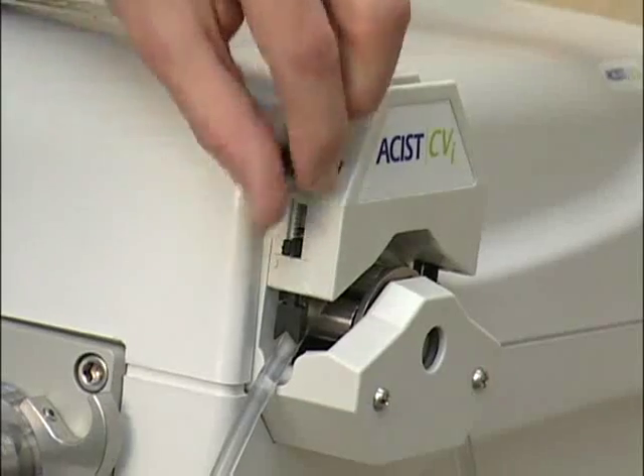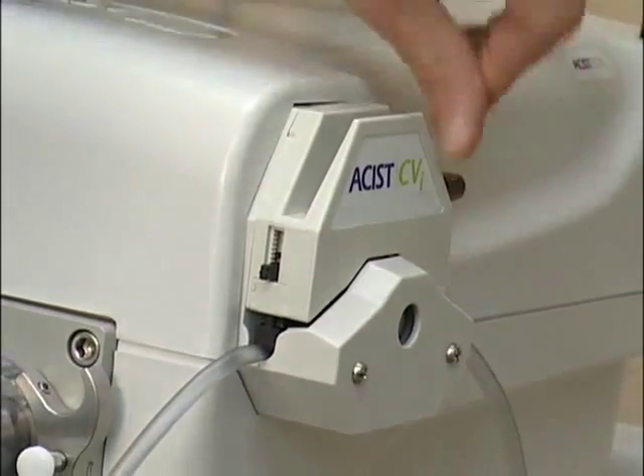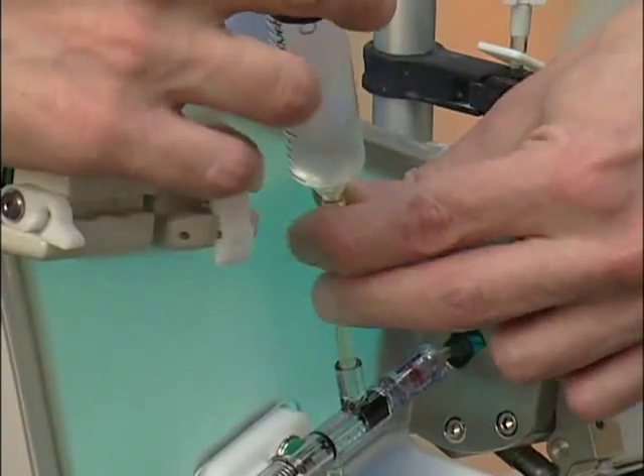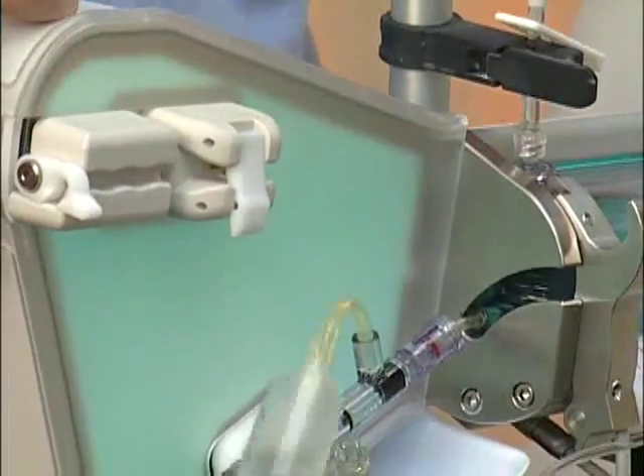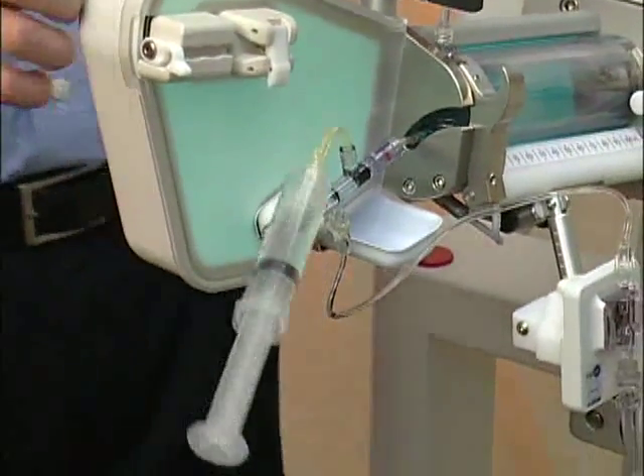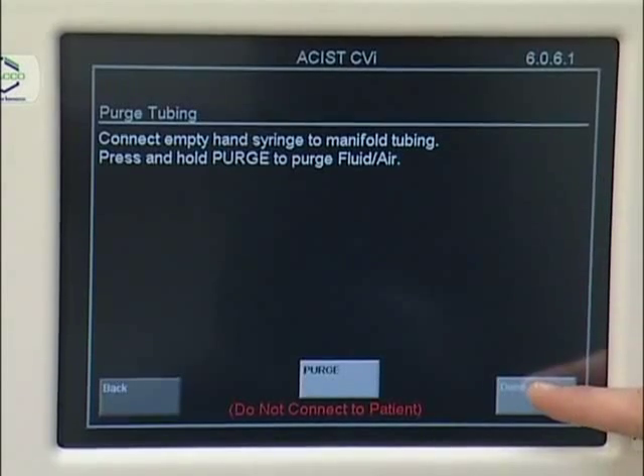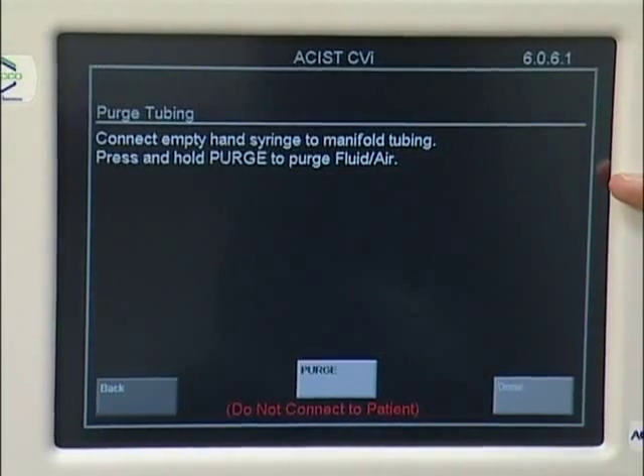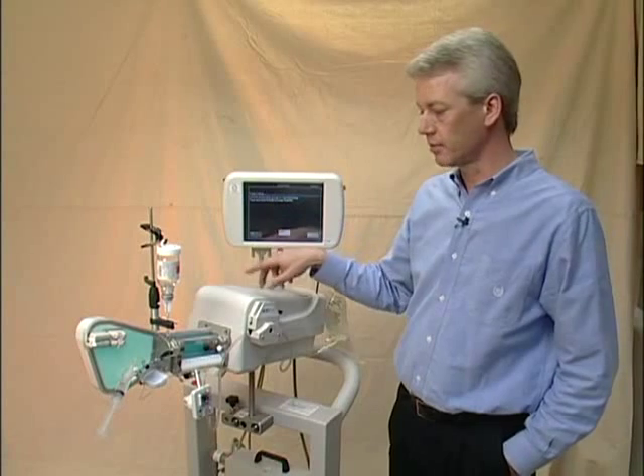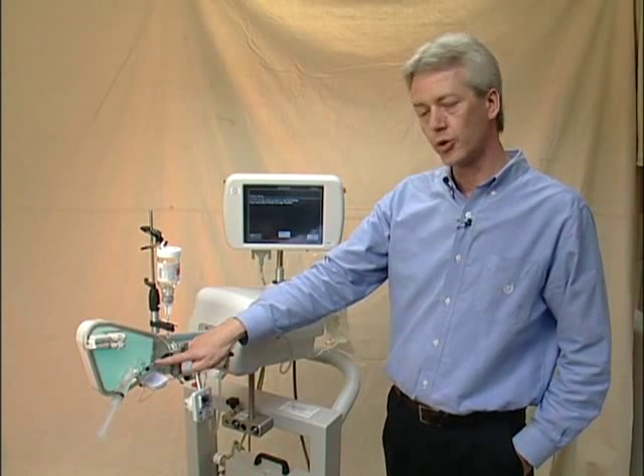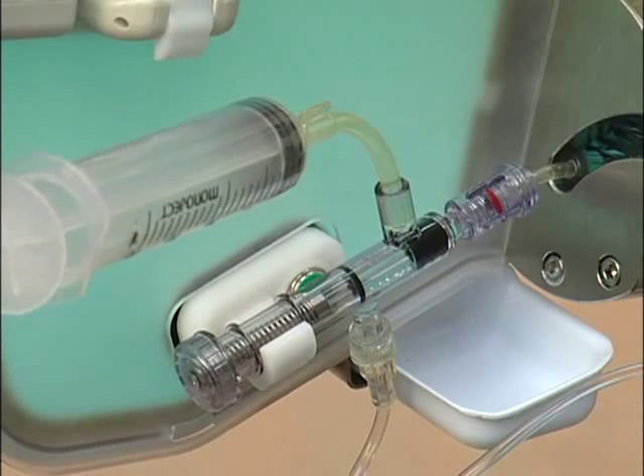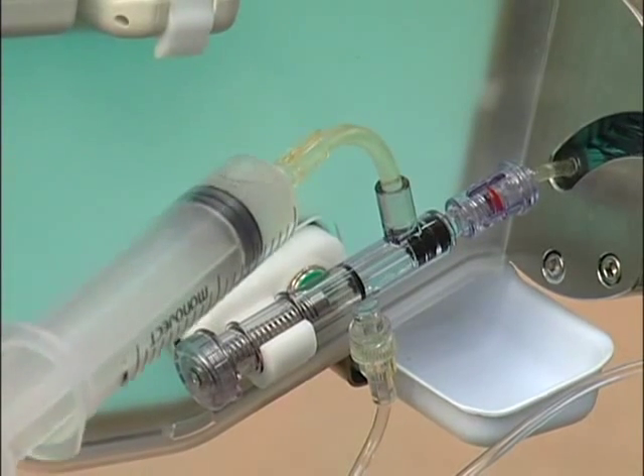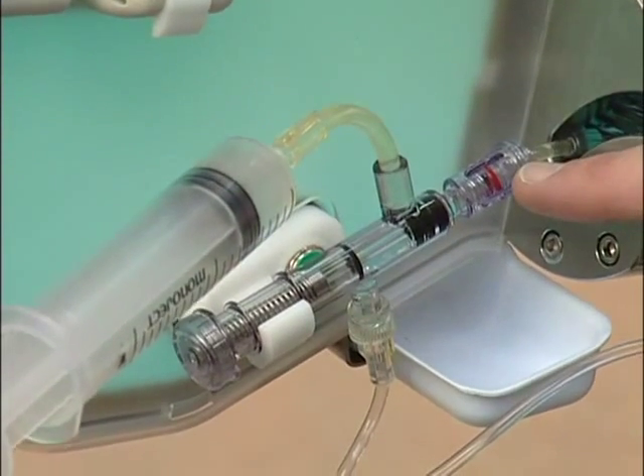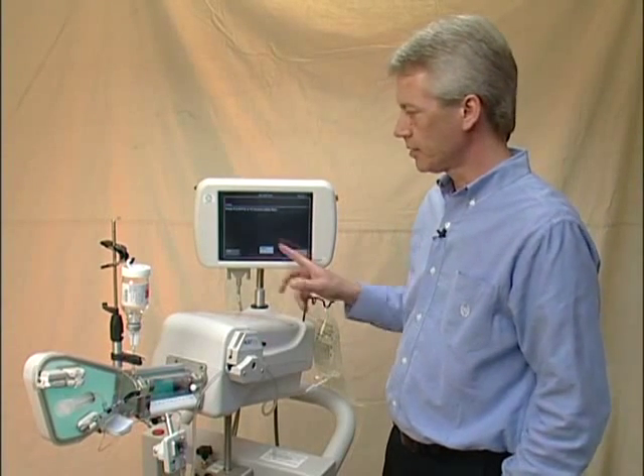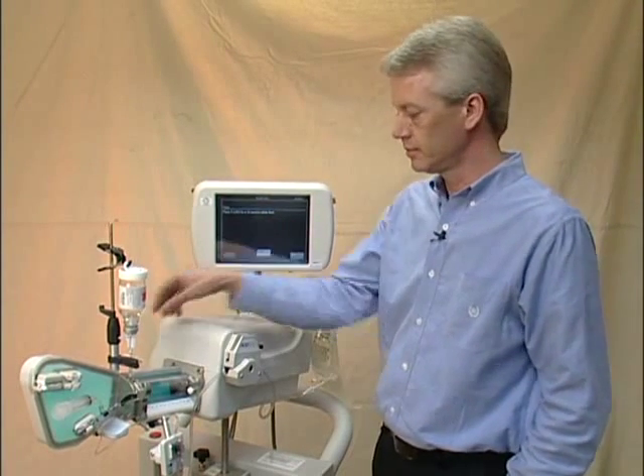Once that step is complete, then the latch can be closed. The hand syringe will be positioned on the end of the tubing until the procedure begins. Once these steps are complete, we'll press done. This brings me to the purge tubing screen. The purpose of the purge tubing screen is to remove any air that would be in our rotating hub. When I press and hold the purge button, you'll see contrast be expelled and remove any air from my rotating hub. Once that step is complete, I'll press done, and it brings me to the flush screen.